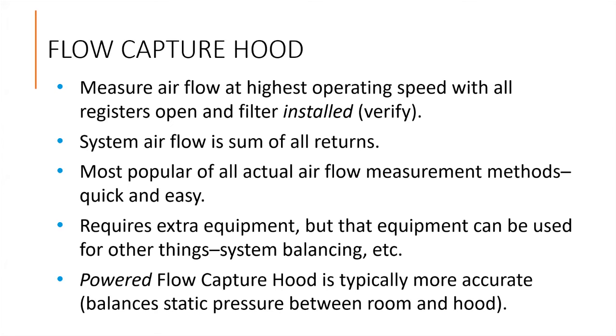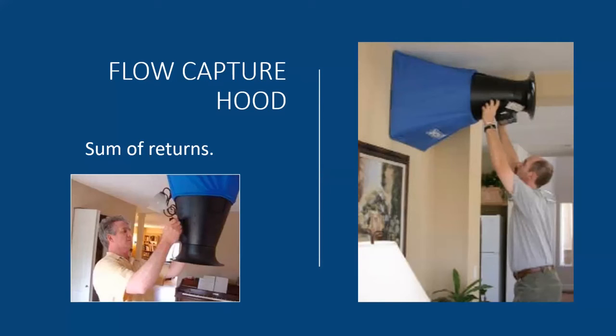The flow capture hood technique uses a balometer or flow hood. With the system running and the filter in, you can measure air flowing through the return register. If there are two or even three returns, you measure each one and add them together for the sum of returns. This is the most popular method because it's quick and easy, and a flow hood can also be used for measuring supply register airflow rates and system balancing. A powered flow hood is considered more accurate because it uses a fan to balance the static pressure between the room and the flow hood. Some of the less expensive flow hoods don't give accurate results at higher CFM flows, so if you need to measure a return register, use a flow hood calibrated to read those much higher airflow rates.